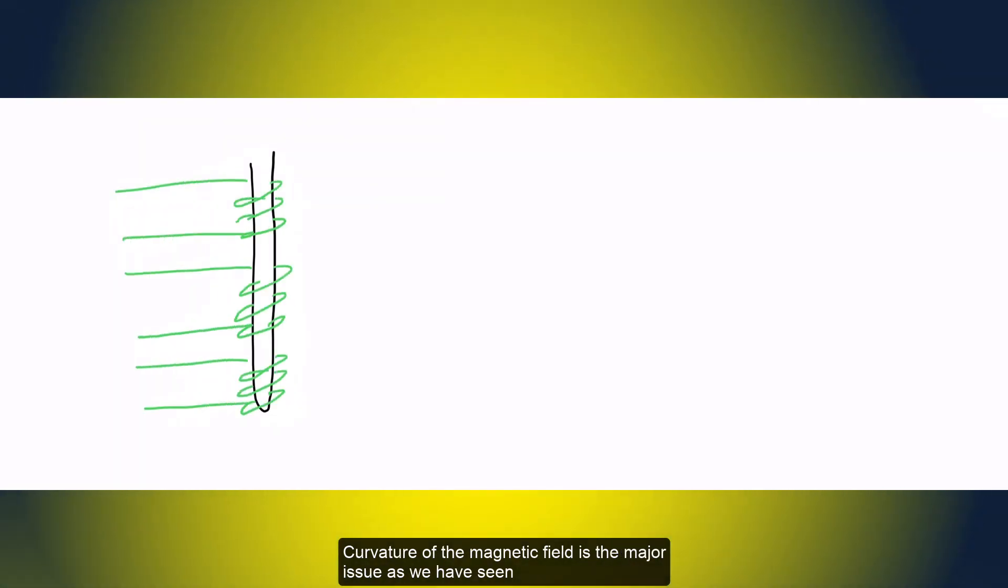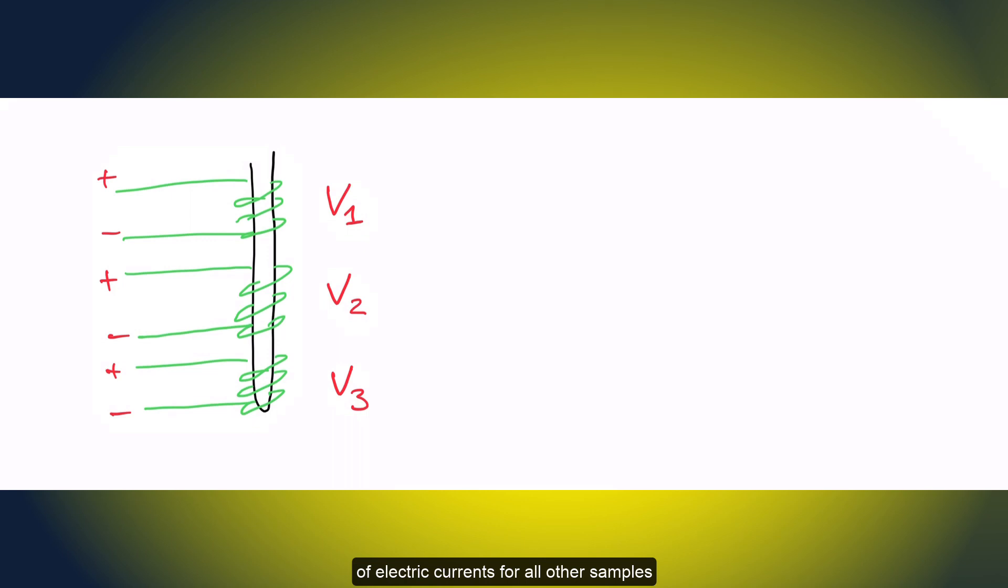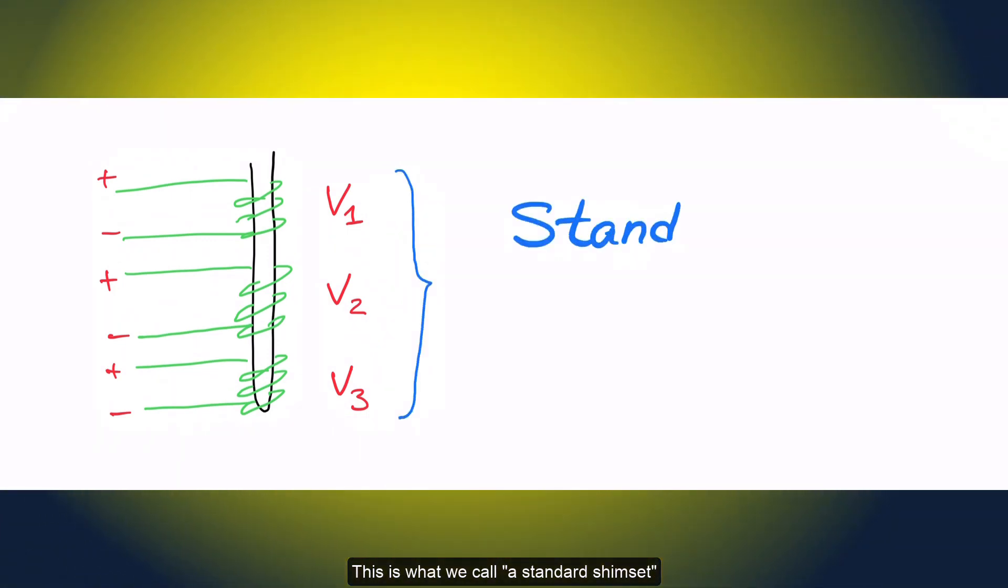Can we shim once and keep perfect shims forever? Yes and no. Curvature of the magnetic field is the major issue as we have seen. We can take it out and simply reuse the values of electric currents for all other samples. This is what we call a standard shim set.